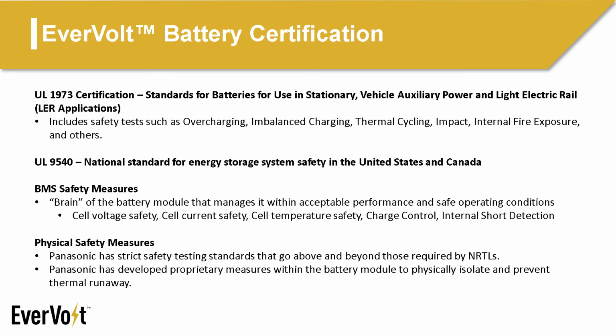There are several certifications required to sell an energy storage system into the US market. The first is UL 1973, which applies to the battery module, in this case the DCB 105. Every DCB 105 undergoes this certification, which includes safety tests such as overcharging, imbalance charging, thermal cycling, impact resistance, and fire exposure tests, along with many others. The next test is UL 9540, which applies to the entire system, in this case Evervolt. It includes similar tests along with many others in addition to those contained in 1973.